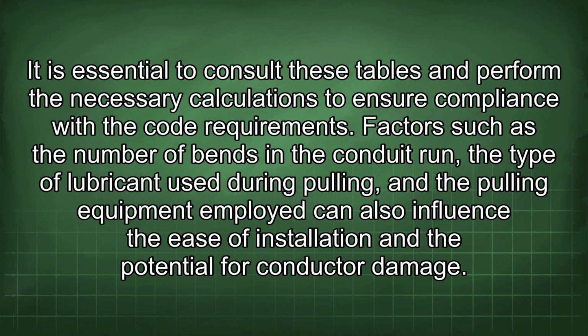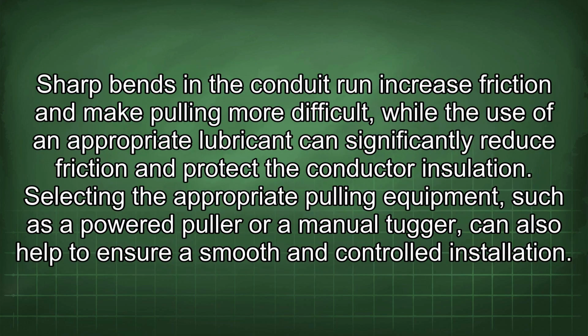Factors such as the number of bends in the conduit run, the type of lubricant used during pulling, and the pulling equipment employed can also influence the ease of installation and the potential for conductor damage. Sharp bends in the conduit run increase friction and make pulling more difficult, while the use of an appropriate lubricant can significantly reduce friction and protect the conductor insulation. Selecting the appropriate pulling equipment, such as a power puller or a manual tugger, can also help to ensure a smooth and controlled installation.